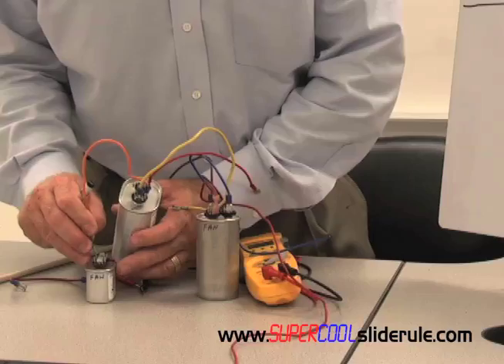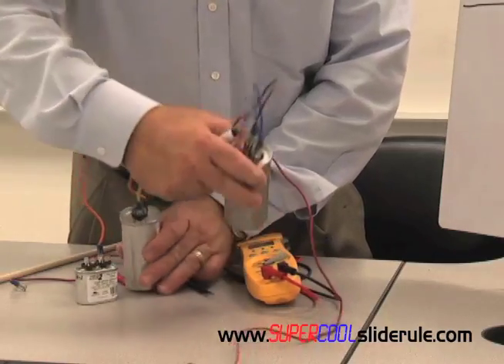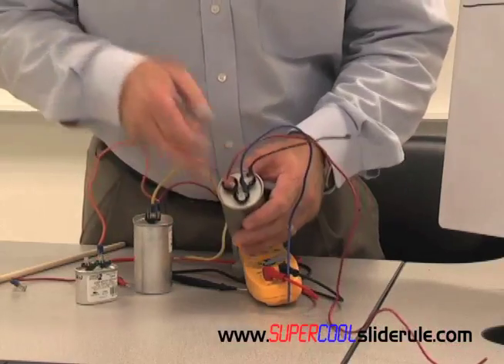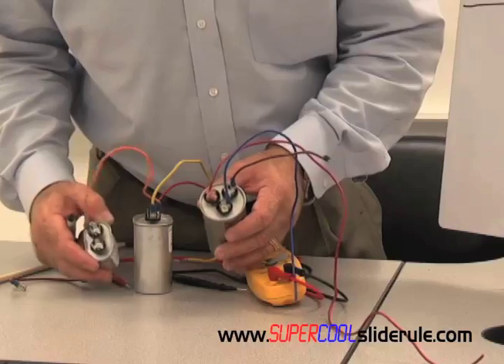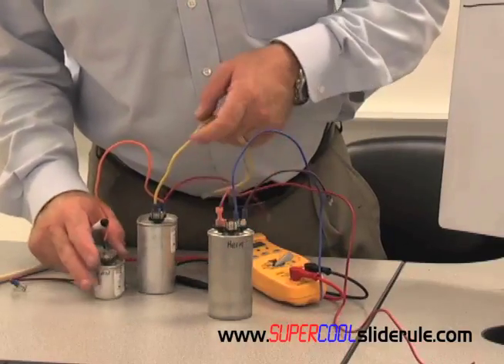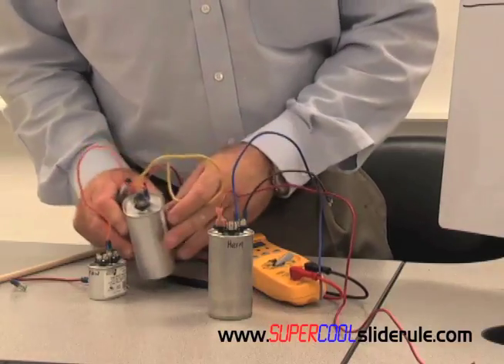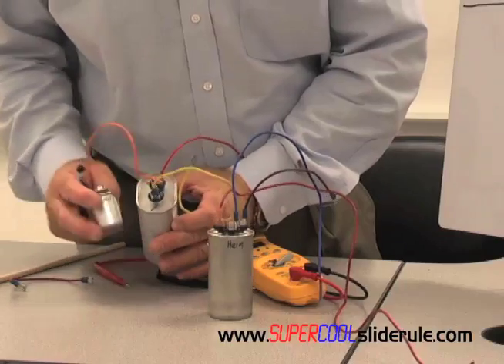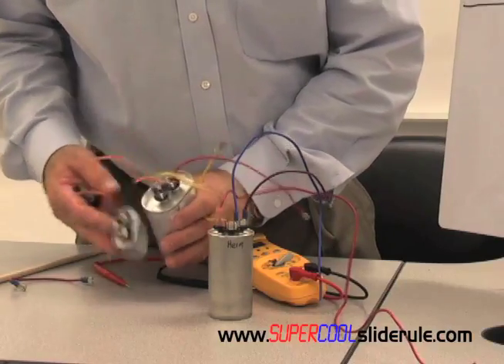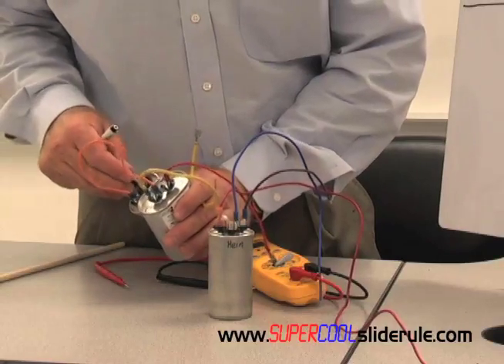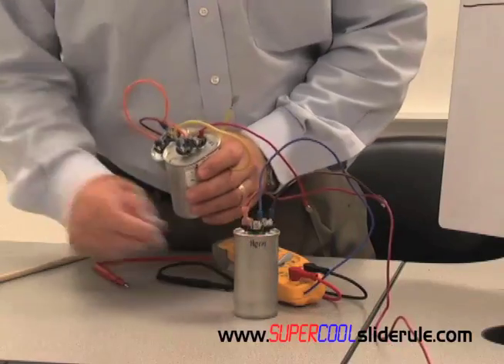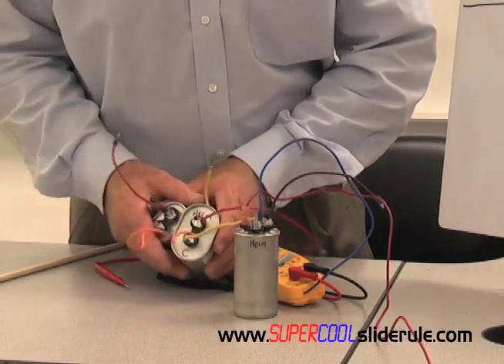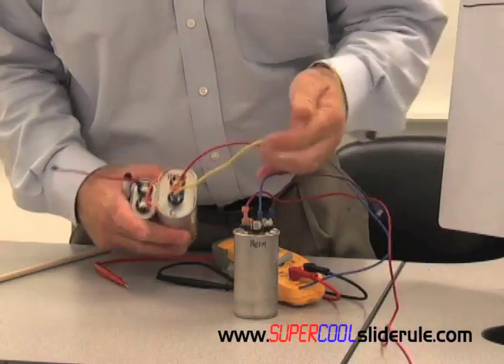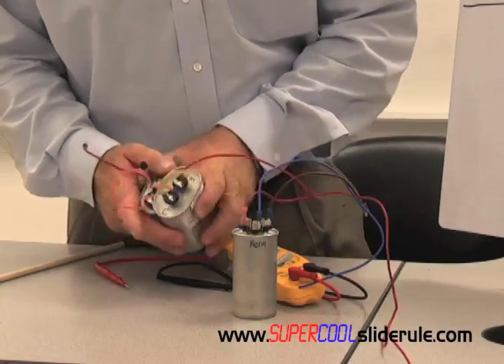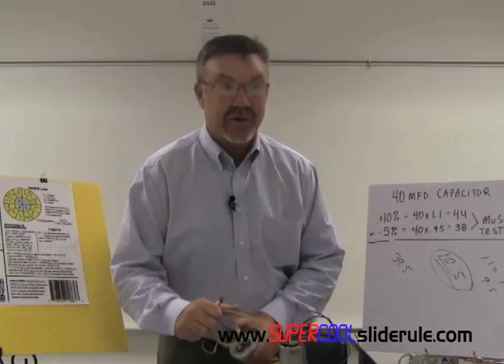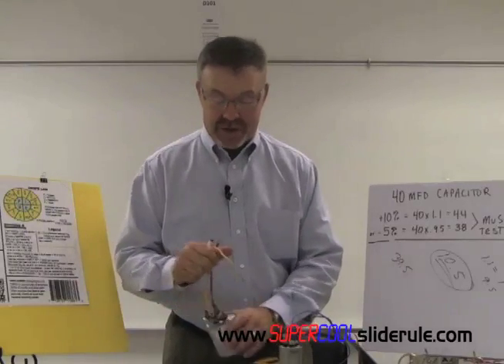So you're going to have to add one jumper wire. This is what you had before. Use a jumper to represent the common. This will go back to the old common. The other side is going to be your Herm, and the unused side will be your fan. So we started with 3 wires. Right now we've got a fan, we've got a Herm, and we've got a common. We are right back to 3 wires, and we made a dual run capacitor with 2 separate capacitors.